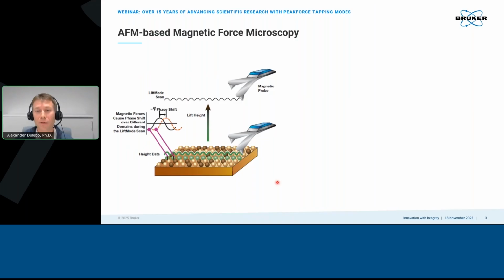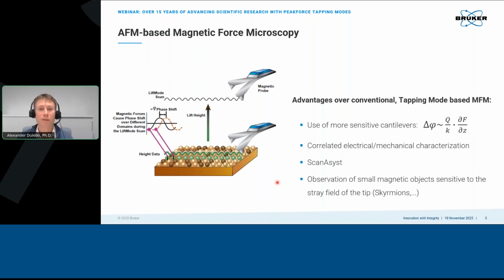And here are a few examples. One of them, of course, is to use more sensitive cantilevers, since we can do PeakForce Tapping. The sensitivity, which we detect by, for example, phase shift on the oscillation, will benefit if the probe spring constant gets lower, which we can actually use and benefit from here. The second, very important, of course, is the possibility to gain all the nanomechanical properties from PeakForce Tapping QNM, like stiffness, adhesion, energy dissipation.